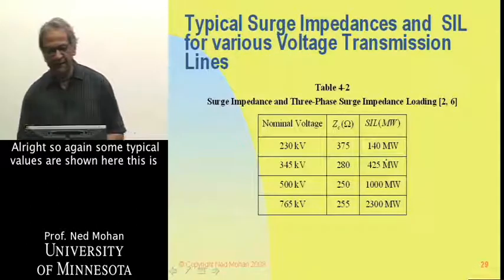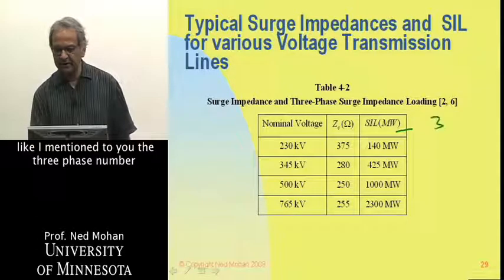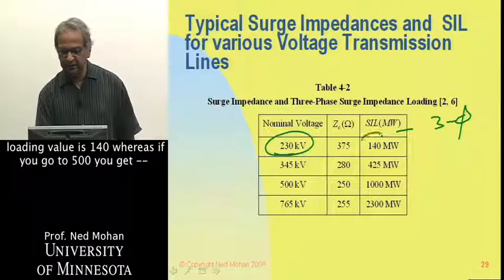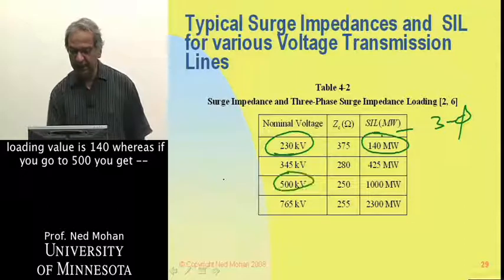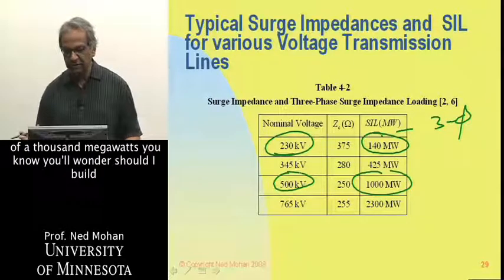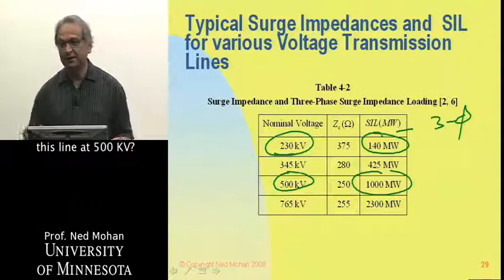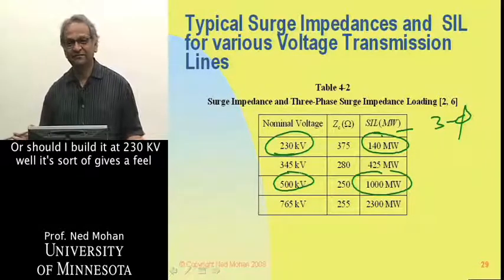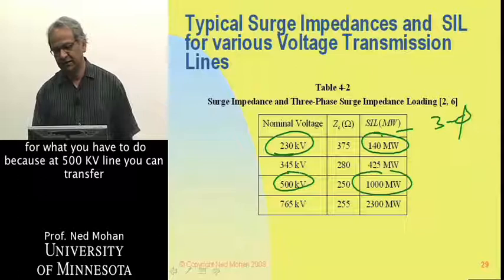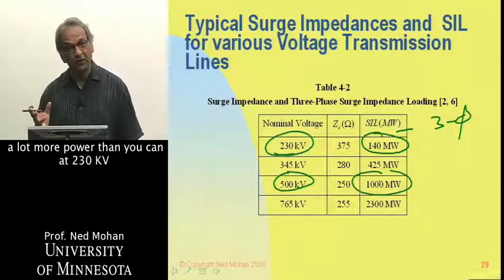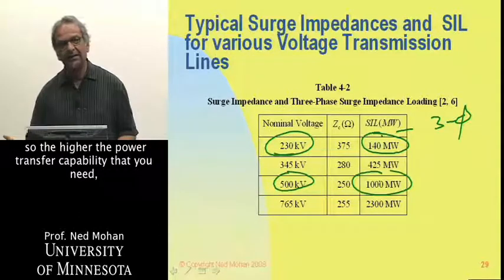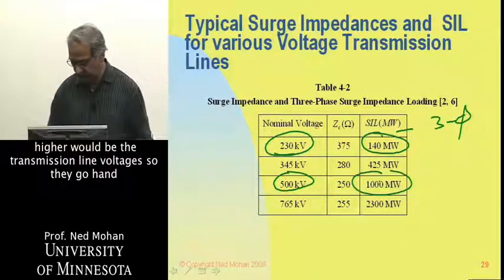All right, so again, some typical values are shown here. This is, like I mentioned to you, is a three-phase number. And you can see that if you have 230 kV line, the surge impedance loading value is 140, whereas if you go to 500, you go to 1,000 megawatts. So if you have to transfer 1,000 megawatts, you'll wonder, should I build this line at 500 kV or should I build it at 230 kV? Well, it sort of gives a feel for what you have to do because at 500 kV line, you can transfer a lot more power than you can at 230 kV. So the higher the power transfer capability that you need, higher would be the transmission line voltages. So they go hand in hand.